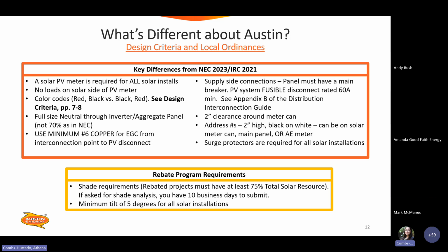A 2-inch clearance around the meter can, and then address numbers have to be 2 inches high, black on white. They can be on the solar meter, the solar meter can, main panel, or the AE meter. And then surge protectors are required for all solar installations. Through the rebate program, we do have shade requirements. So you must have 75% or greater for the total TSRF. And if we do ask for a shade analysis, y'all have 10 business days to submit that. And then a minimum of 5-degree tilt for all solar installations.